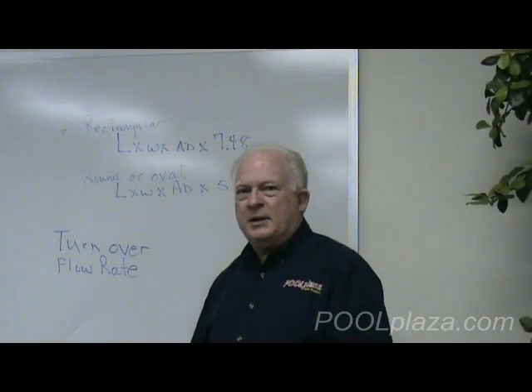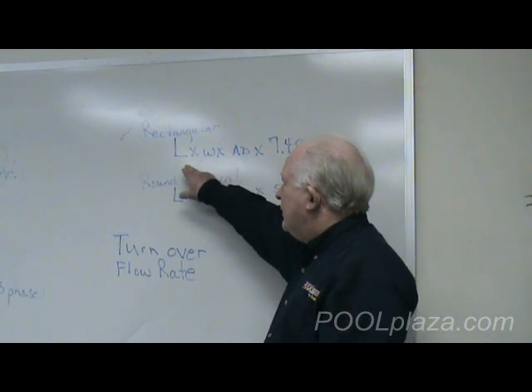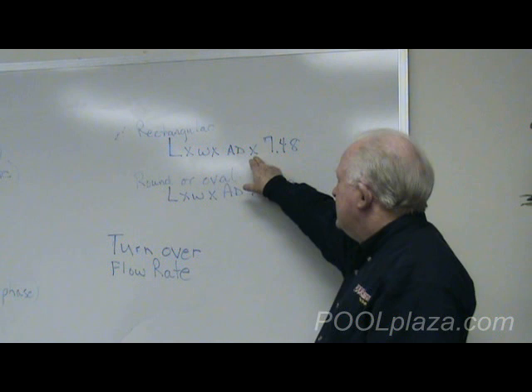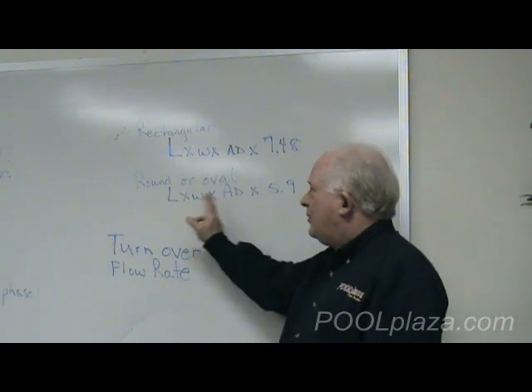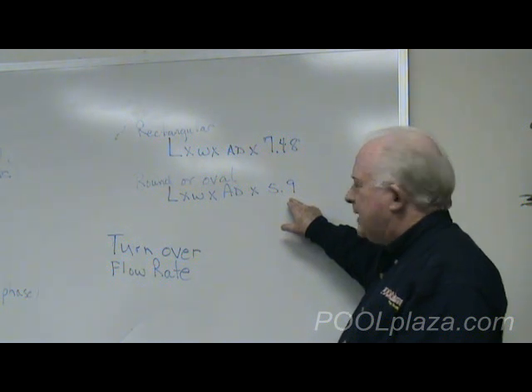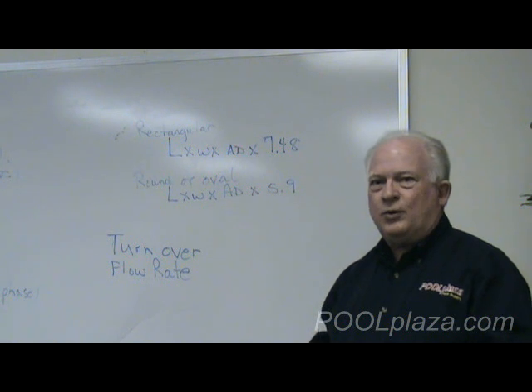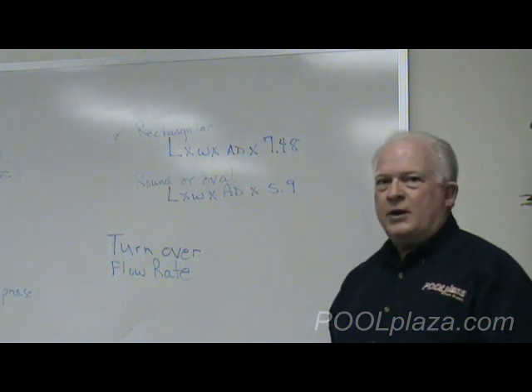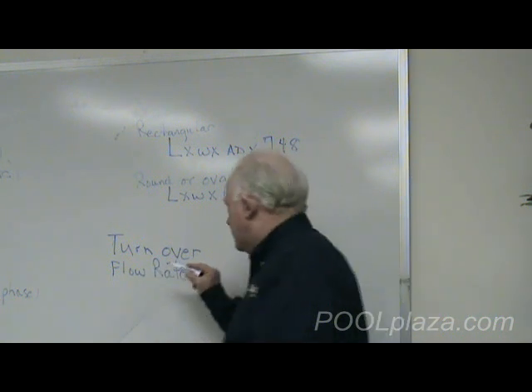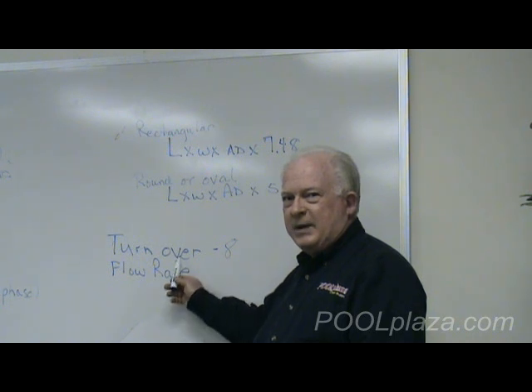It's very important when selecting a pump that you select one that can handle the volume of water in your pool. The formula for rectangular pools is length times width times average depth times 7.48. For round or oval pools, it's length times width times 5.9. Get that number as close as you can. For residential pools, you want to be able to turn over the entire amount of water in the pool once every eight hours, and you want a flow rate that the pump can provide to make that turnover happen.